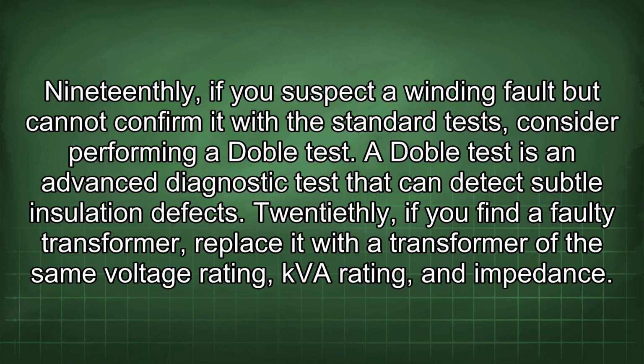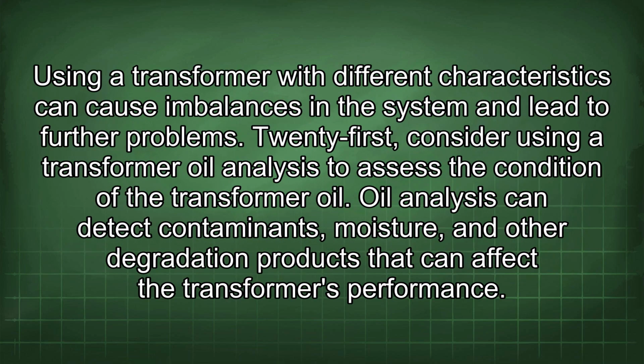20thly, if you find a faulty transformer, replace it with a transformer of the same voltage rating, kVA rating, and impedance. Using a transformer with different characteristics can cause imbalances in the system and lead to further problems. 21st, consider using a transformer oil analysis to assess the condition of the transformer oil. Oil analysis can detect contaminants, moisture, and other degradation products that can affect the transformer's performance.